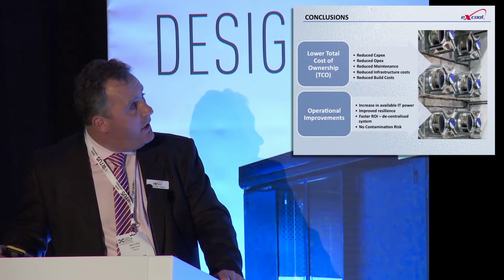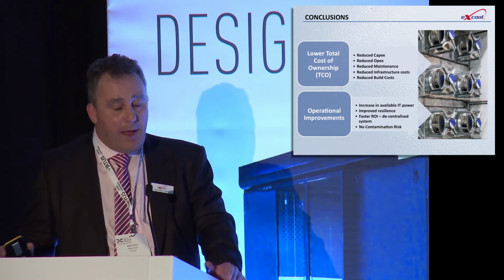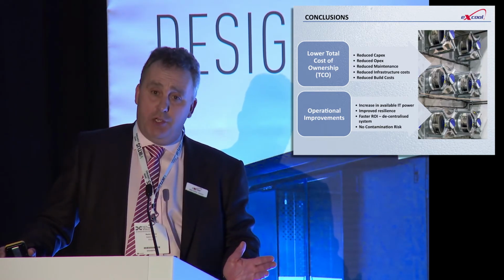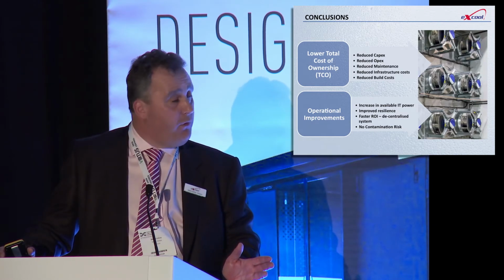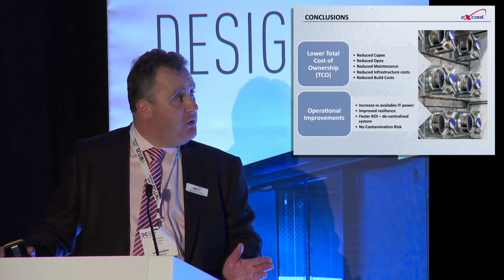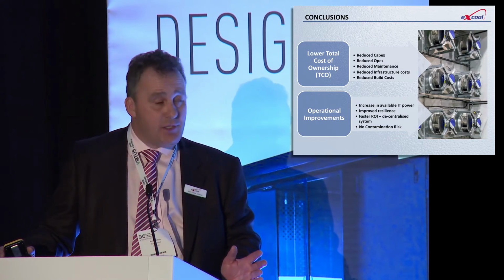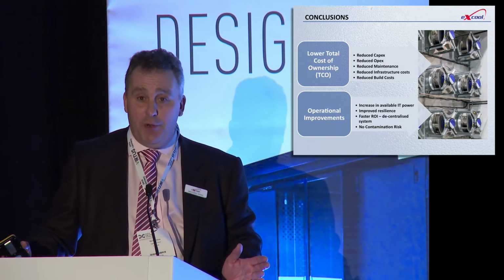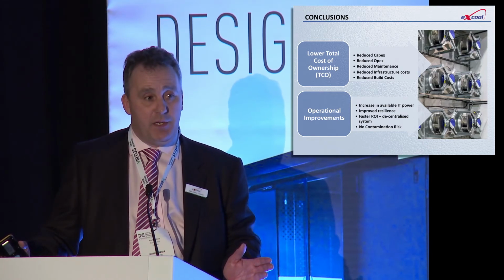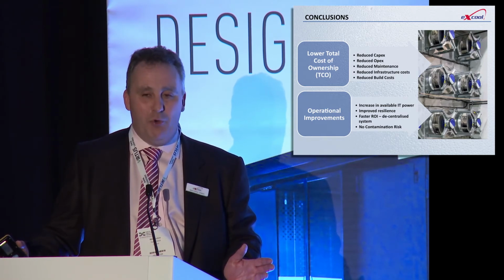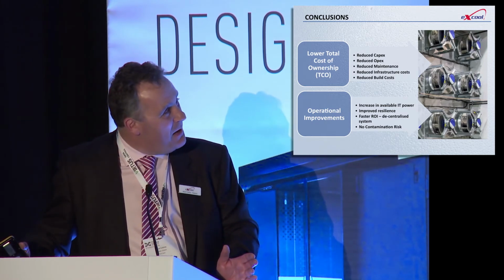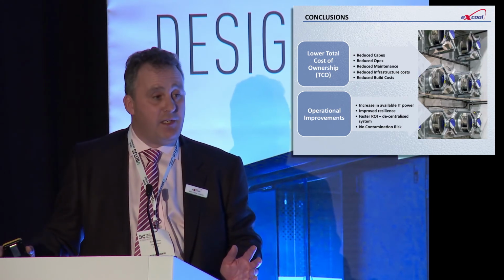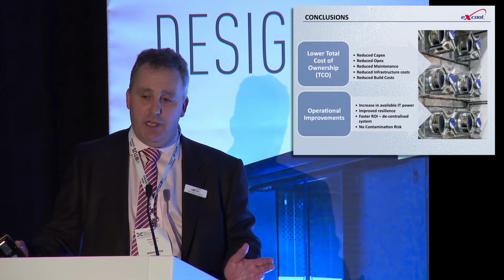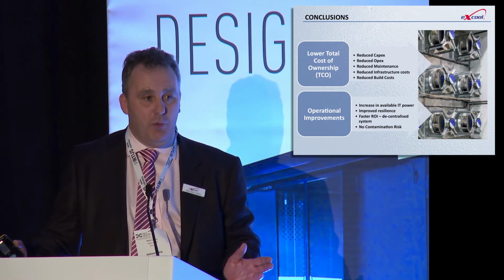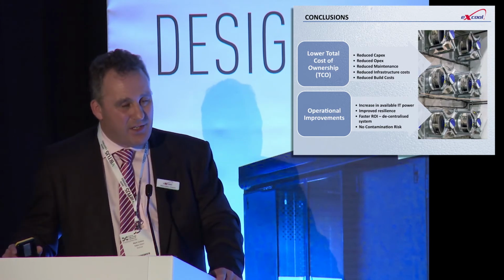So just in summary, to conclude what I've just been talking about, there's a lower total cost of ownership with this product. You've got reduced capital expenditure, reduced operating expenditure, reduced maintenance costs, reduced infrastructure costs. Your building can be smaller because you've taken the CRAC units out of the space. Invariably, what tends to happen is that because there's more power available, people put more racks into the space. And you can reduce your build costs. You could build a smaller data center because you don't need space for the internal cooling equipment. Again, most people will stick with the same size data center and put more racks in and get more IT out of it.